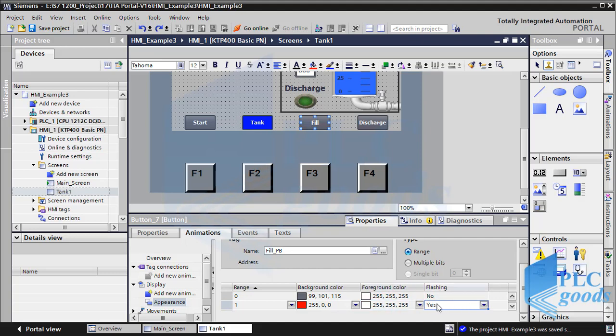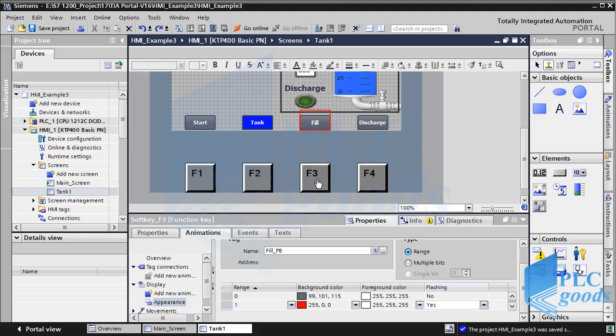If you notice, here we have four function keys: F1, F2, F3, and F4. These function keys can be used to either actuate an input, change the activated screen, or for any other purpose like buttons. The basic idea behind these function keys is that we can use them as a local or global assignment. Let's define a local function — tank filling — for the F3 key, like its upper fill button.